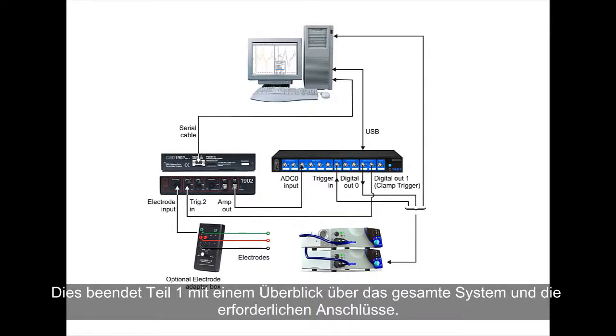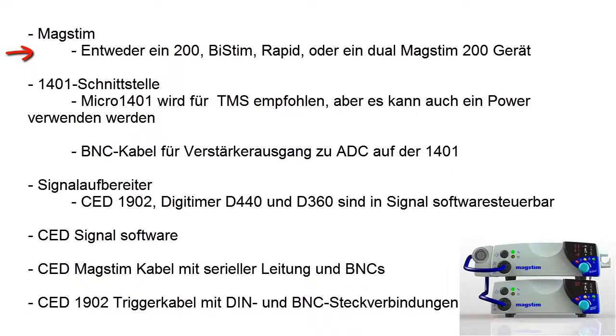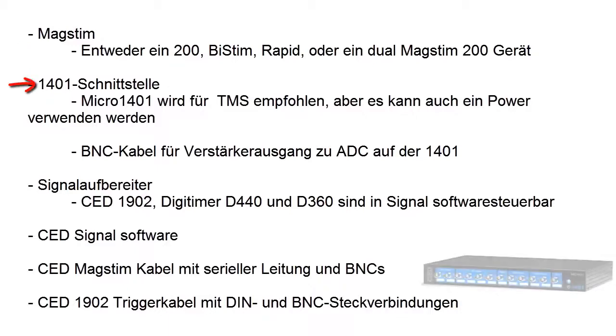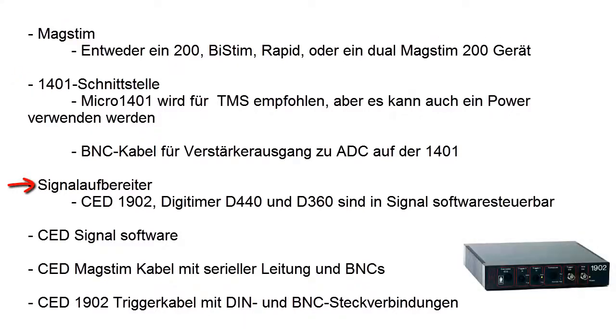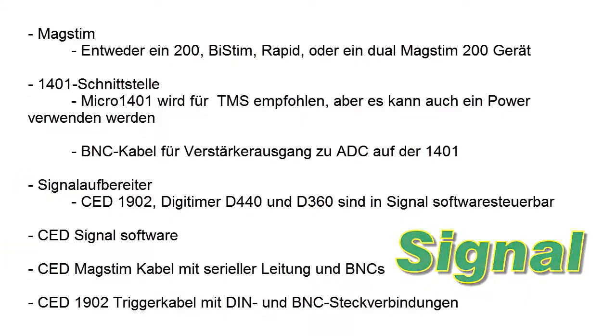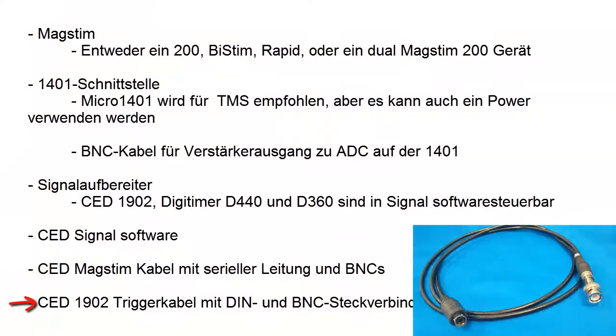This concludes part 1, looking at the whole system and the required connections. To summarise, you will need a MagStim — either a 200, BiStim or Rapid device, or dual MagStim 200 devices — a 1401 interface (the Micro 1401 is recommended for TMS, but you can use a Power 1401), BNC cables for amplifier output to ADC waveform input on the 1401, a signal conditioner (the CED1902, Digitimer D440 and D360 are software controllable in signal), a copy of CED signal software, a CED MagStim cable with serial line and BNCs, and a CED 1902 trigger cable with DIN and BNC connectors.